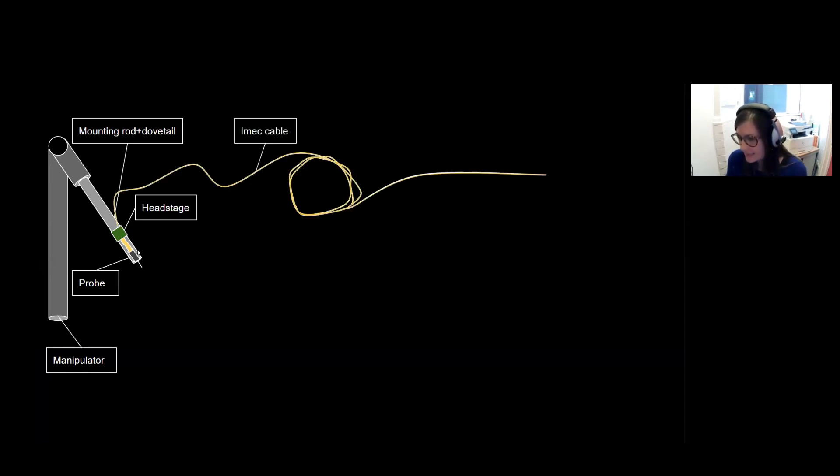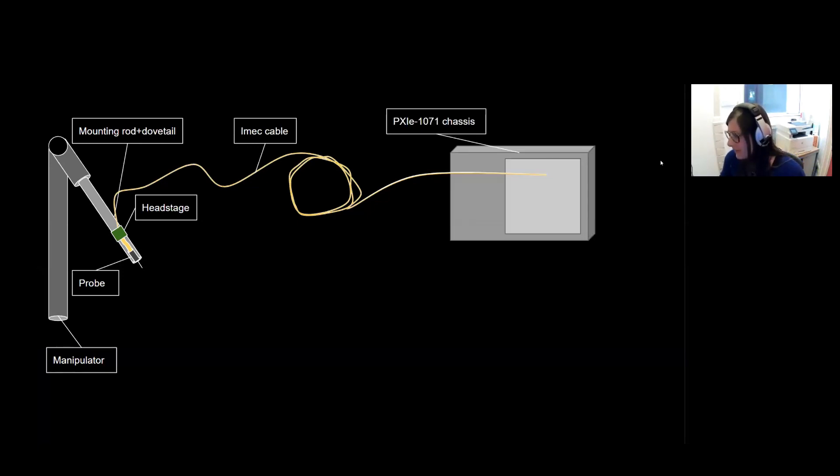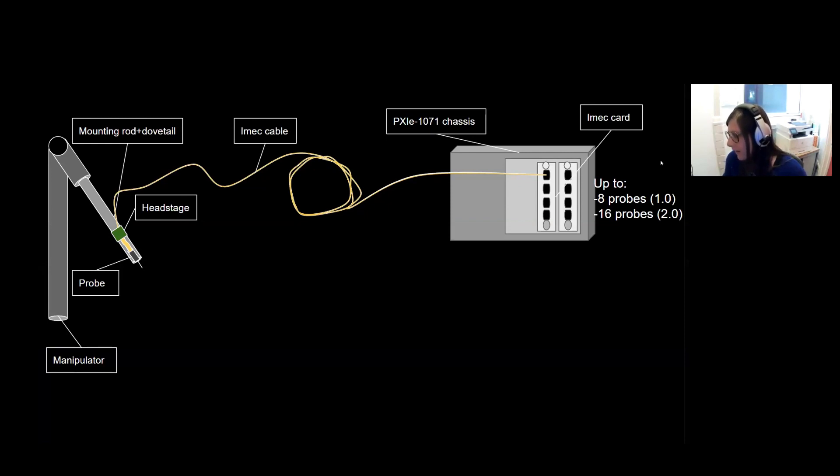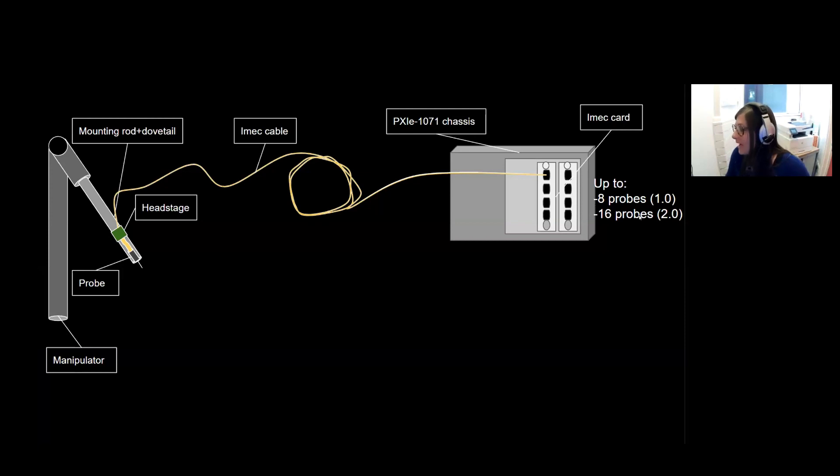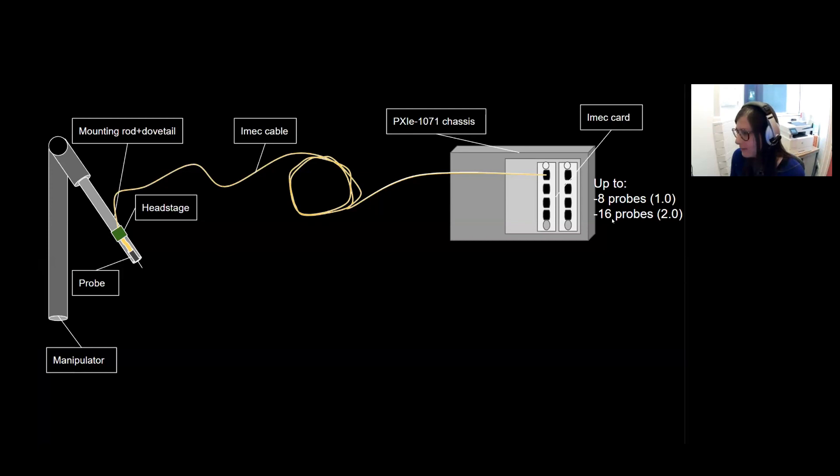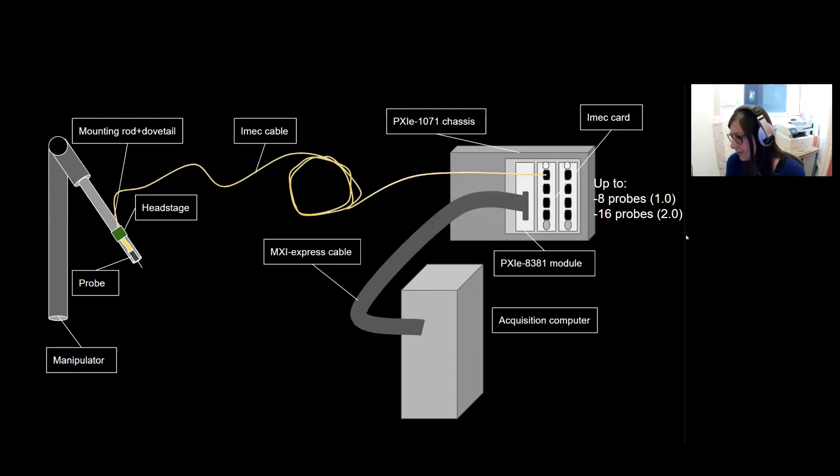Data is then transferred via an IMEC cable in most cases to a PXIE chassis where you can record up to eight probes. You can have up to two of these IMEC cards that each have four slots, which means you can have up to eight probes for 1.0 probes and up to 16 for 2.0. Again, because you can put two probes per headstage. And this data is then transferred to an acquisition computer via an MXI Express cable.